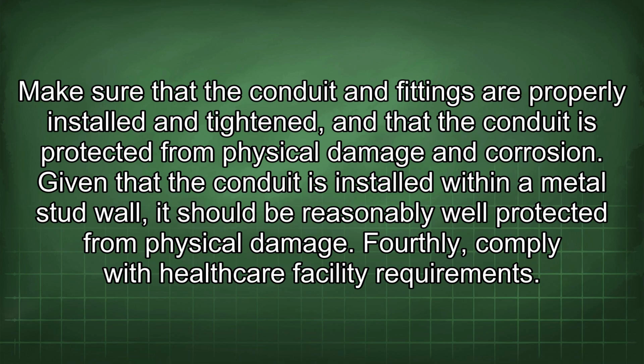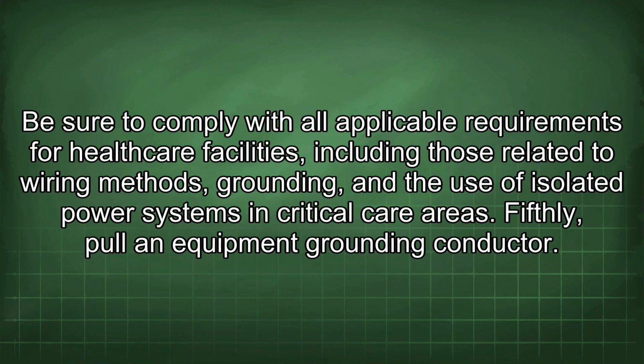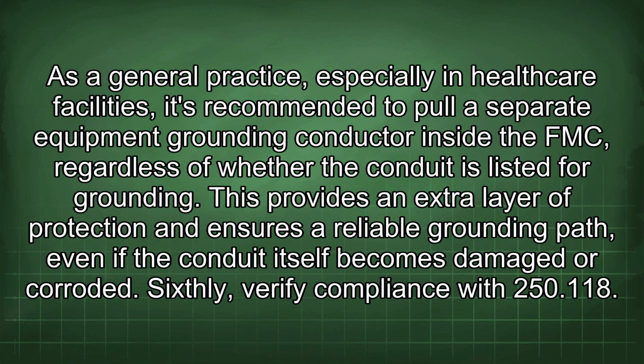from physical damage. Fourthly, comply with healthcare facility requirements. Be sure to comply with all applicable requirements for healthcare facilities, including those related to wiring methods, grounding, and the use of isolated power systems in critical care areas. Fifthly, pull an equipment grounding conductor. As a general practice, especially in healthcare facilities, it's recommended to pull a separate equipment grounding conductor inside the FMC, regardless of whether the conduit is listed for grounding.